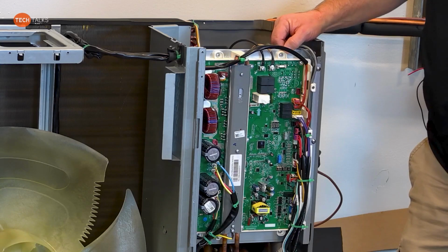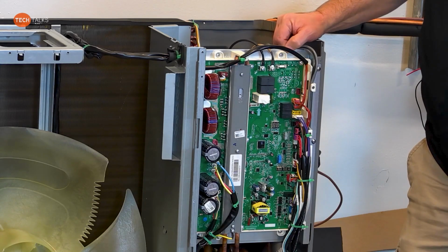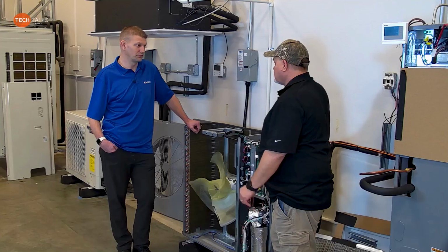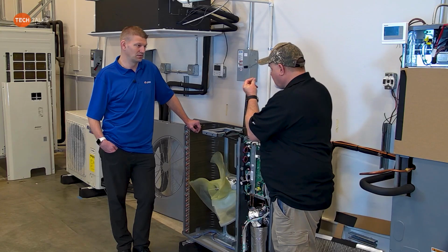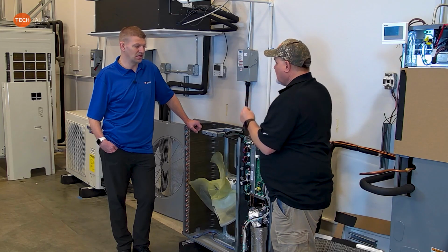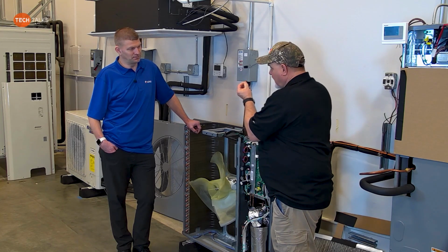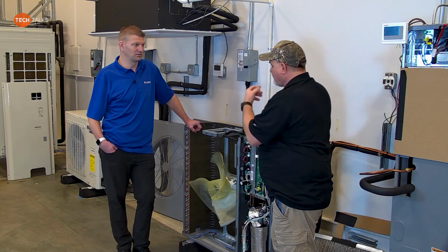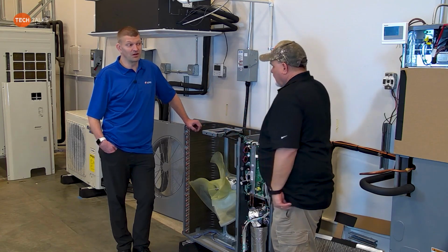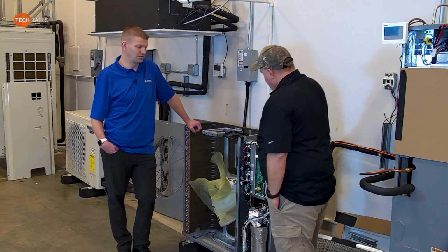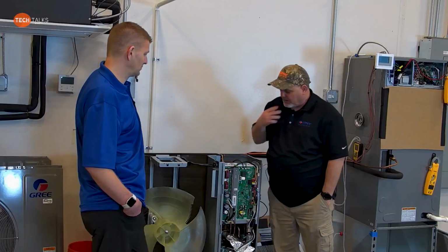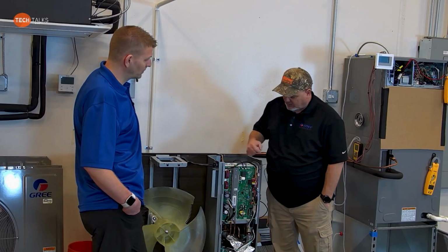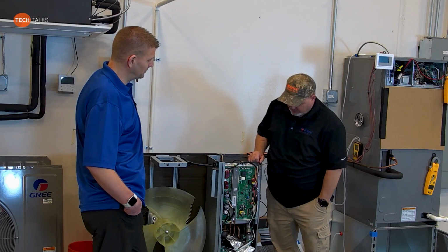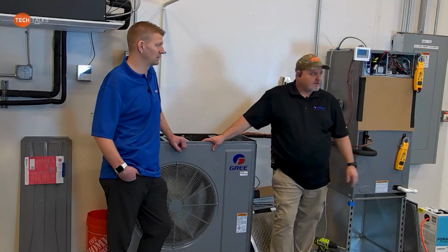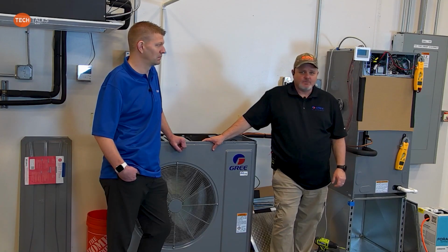I actually think it's a little trickier on the air-cooled inverters, because you have the pads on the back of it. You got to make sure that's all clean, because when it burns, you could get some solder spots in that paste. If you don't clean it off, you could have potential short. Getting the screws all the way in. Yep, getting the screws all the way in. I think this is going to be a whole lot better. So I think you guys will find that this will be a lot easier to change if you got to change the whole board. Like I said, guys, with GREE, we're always by your side.